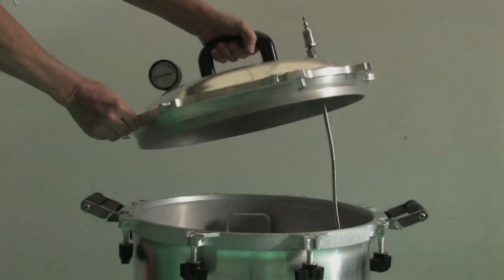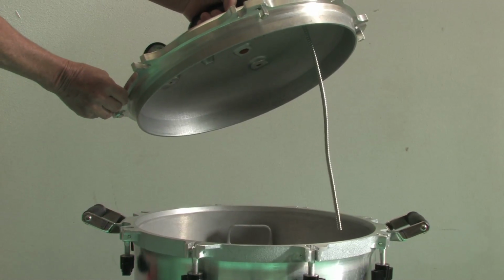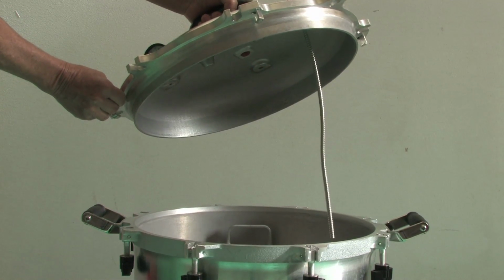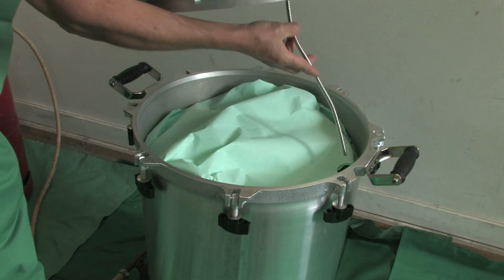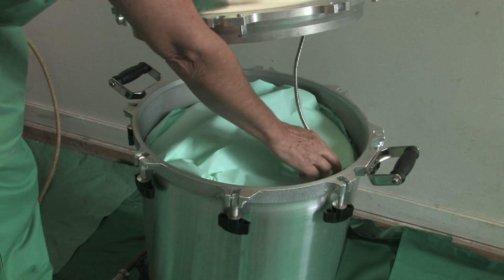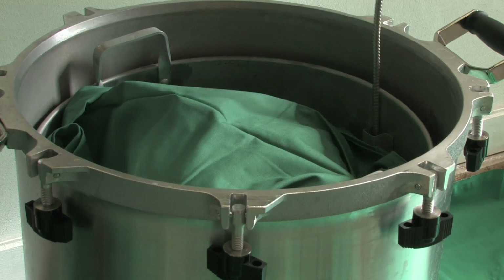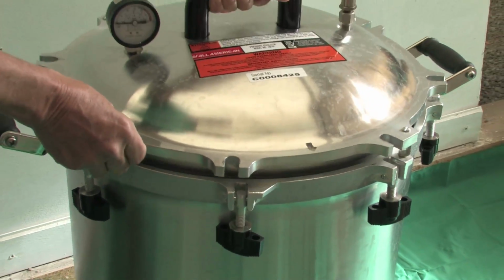Note: check the condition of the flexible metal tube at least once a month. Make sure it's not clogged with limescale, so that air can leave the autoclave. Clean it if necessary with a small channel cleaning brush or a thin wire. If the flexible metal tube is too encrusted with limescale, replace it.